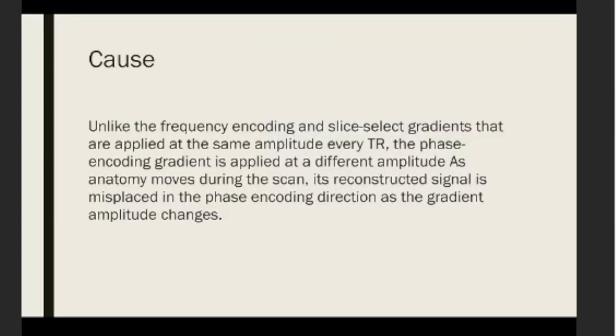The cause of this artifact is that the frequency encoding and slice select gradients are applied at the same amplitude every repetition time, but the phase encoding gradient is applied at a different amplitude. As anatomy moves during the scan, its reconstructed signal is misplaced in the phase encoding direction as the gradient amplitude changes.